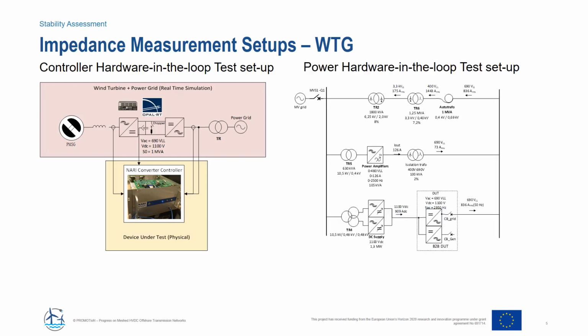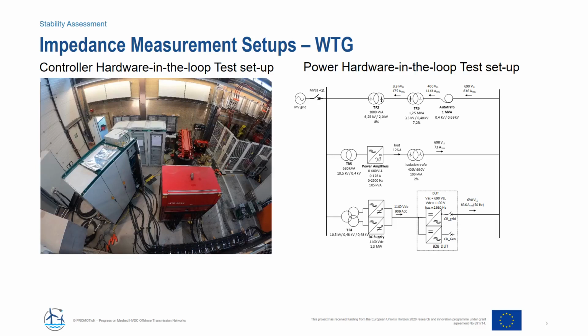To the right, we show a diagram of a power hardware in the loop testing. So this is actually the real 1 megawatt wind turbine converter. And the system is perturbed by harmonic sources at different frequencies, and we measure the voltage and the current at the terminal. This is the lab picture. The white cabinet hosts the 1 megawatt converters for the wind turbine.